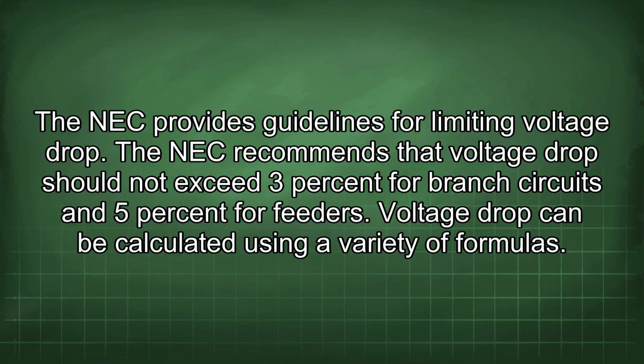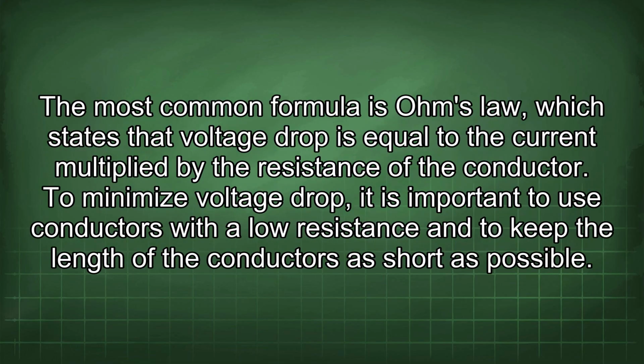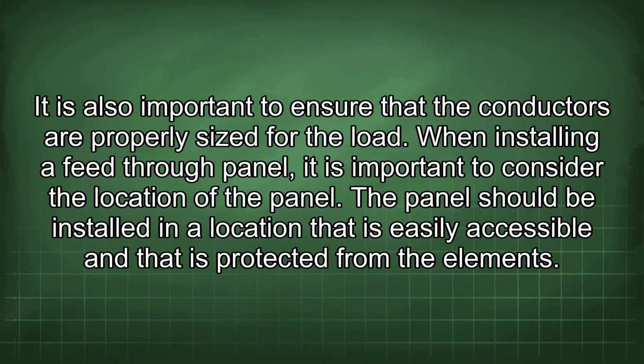Voltage drop can be calculated using a variety of formulas. The most common formula is Ohm's law, which states that voltage drop is equal to the current multiplied by the resistance of the conductor. To minimize voltage drop, it is important to use conductors with a low resistance and to keep the length of the conductors as short as possible. It is also important to ensure that the conductors are properly sized for the load.